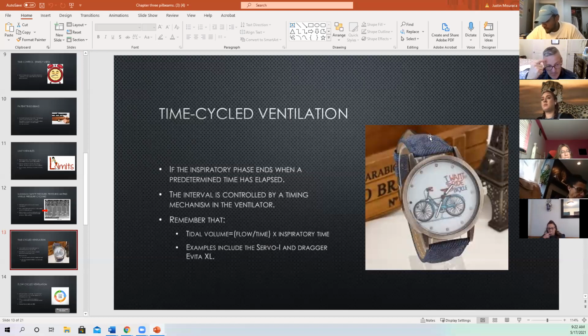So stop for a second and go, pressure limited. What does that mean? It can only go to a certain pressure. Time cycled. It cycles for a certain amount of time, right? So the interval is controlled by a timing mechanism in the ventilator. And remember that tidal volume equals flow times inspiratory time. So if you just look at flow over a certain period of time, it'll give you a tidal volume. The Servo-i and the Dräger, well, there's a ton of ventilators. You have an I time, it's going to cycle that way.